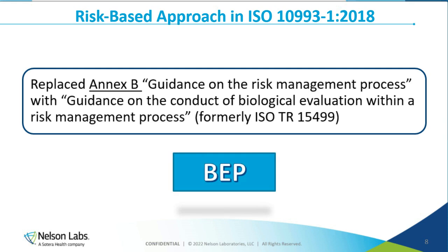Okay. And then because of this, because it's now not just a checkbox approach, right? Now we have this view of, let's take a look at the device, see how it's used, what is the available information, and then you define the set of tests if needed. And that really drives home the message that you actually do need to start with a biological evaluation plan, right? The BEP. So that has also been brought into the standards.